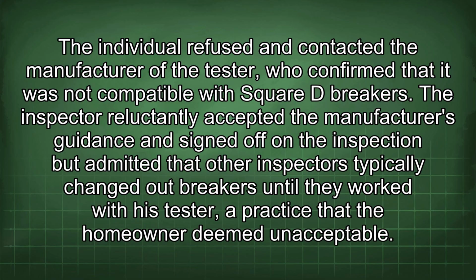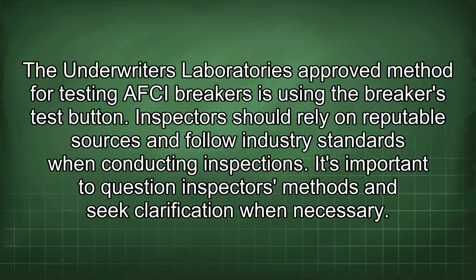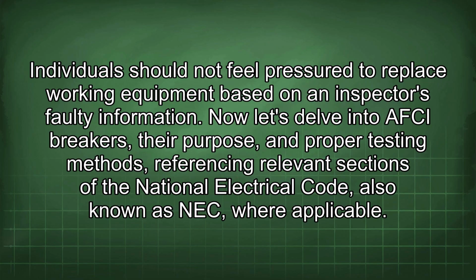The inspector reluctantly accepted the manufacturer's guidance and signed off on the inspection, but admitted that other inspectors typically changed out breakers until they worked with his tester, a practice that the homeowner deemed unacceptable. The Underwriters Laboratories approved method for testing of AFCI breakers is using the breaker's test button. Inspectors should rely on reputable sources and follow industry standards when conducting inspections. It's important to question inspectors' methods and seek clarification when necessary. Individuals should not feel pressure to replace working equipment based on an inspector's faulty information.